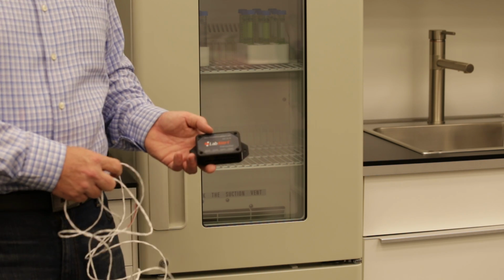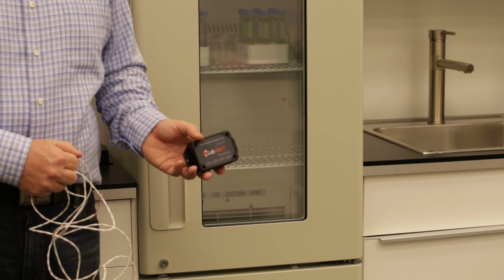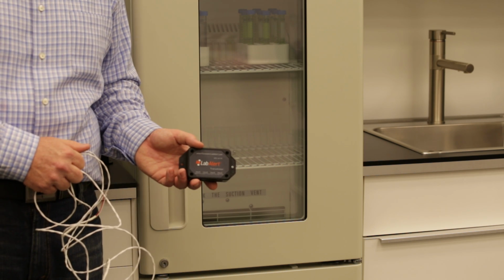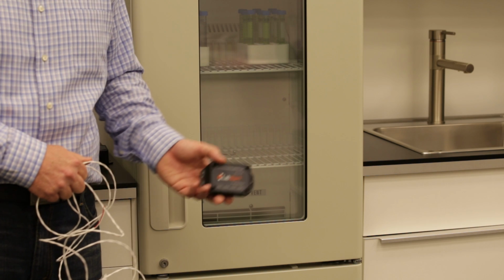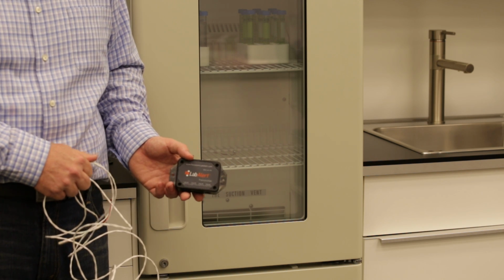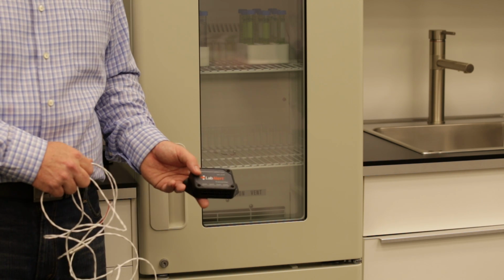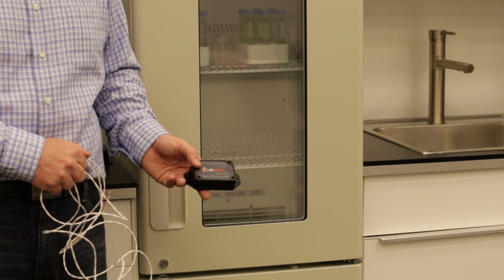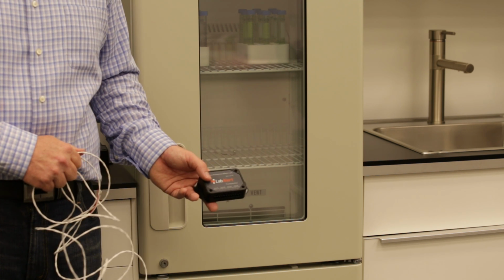But in most applications, you're not going to want to go to too many. There are going to be some cases where you do if they want to read multiple temperatures from the same piece of equipment. But normally you don't want to go more than probably 2 temperature sensors per transmitter.